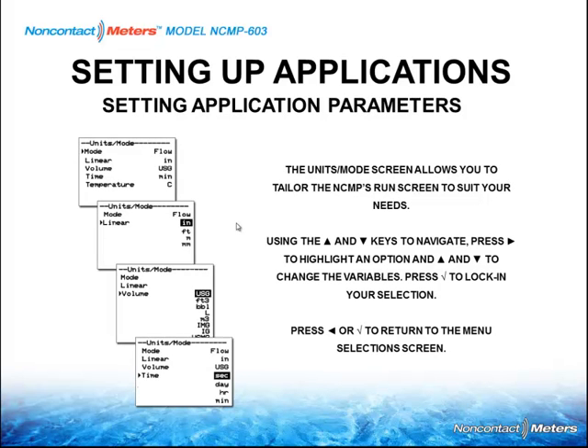After that, with every device you have to program it for the units that you're going to work in. In this case, we're going to select English or metric. We want to read the flow in inches for our engineering unit, or you could read it in metric if you wanted to. We want the volume to read in US gallons. As far as the time factor, you can read it in seconds, hours, and days. Most people select gallons per minute.